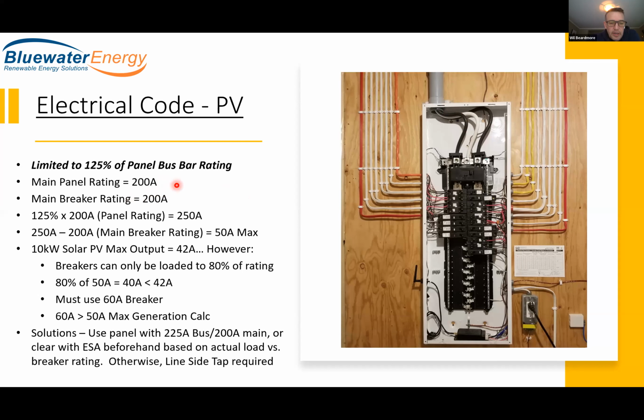So if we have a panel that's rated at 200 amps, we have to factor in what the grid can supply that panel already. If we have a 200 amp main breaker and a 200 amp panel, then the grid can actually supply 200 amps, because that main breaker will allow 200 amps to hit that bus bar. If we take 125% of 200 amps, we're allowed 250 amps onto that panel. The grid can supply 200 amps of that because of the main breaker, so that leaves us 50 amps of room to feed onto that load center.